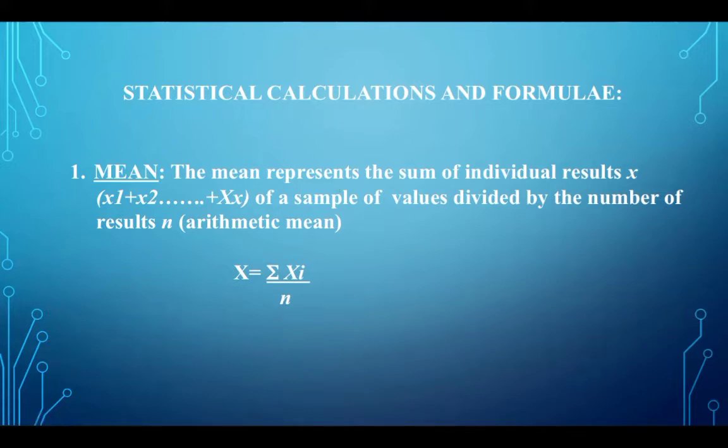Now, Kavita, the situation is, we are saying one standard deviation is acceptable to us, right? Suppose the first month your mean is 99.7. Second month your mean is 99.4. Third month your mean is 99.2. Fourth month your mean is 99.0. Both are within one standard deviation. But they are showing a trend.